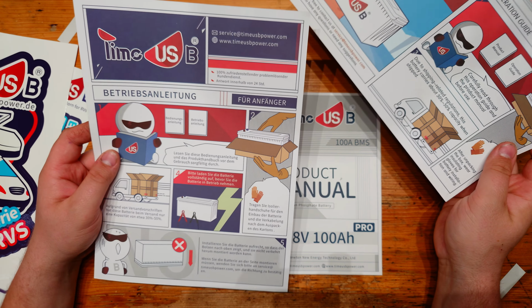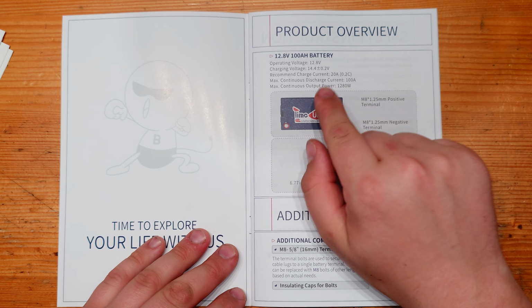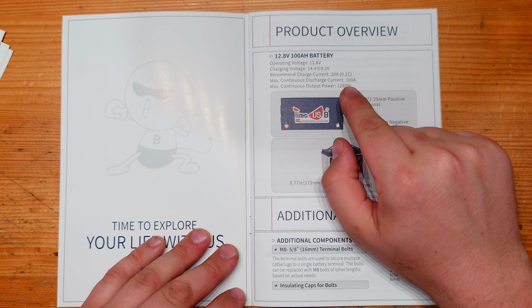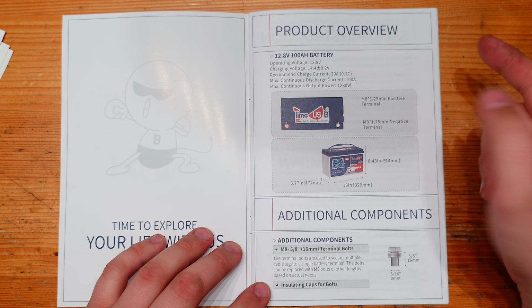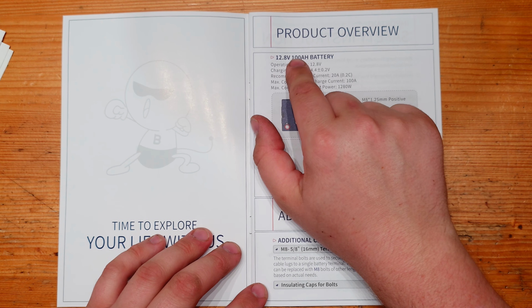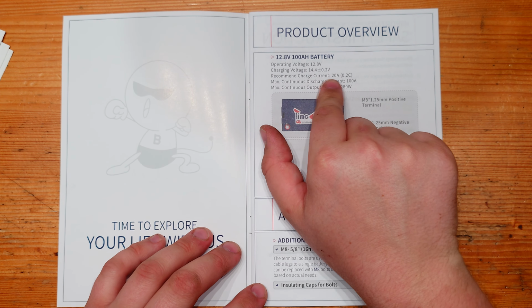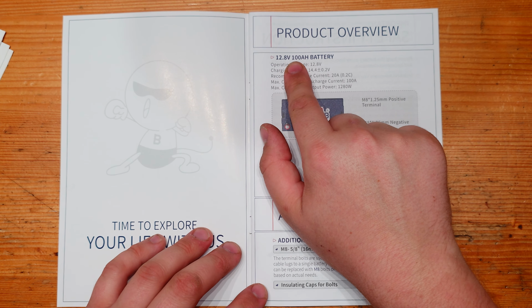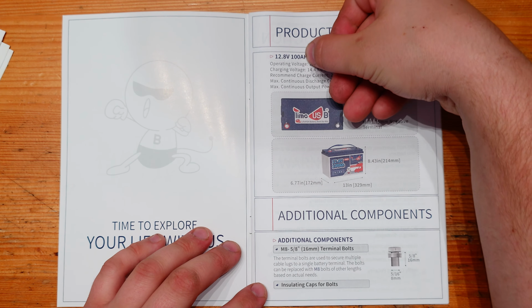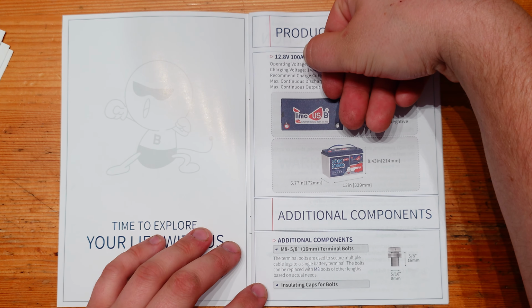All the parameters of the battery can be found on the TimeUSB webpage or in this manual. The recommended charge current is here just for longevity purposes, as lithium ion and LiFePO4 cells are best charged with 0.2C current, which is 0.2 times 100 amp hours, giving 20 amps. It's very easy: you just multiply the capacity, the 100 amp hours, with the C number. So 0.2 times 100 is 20, and the C just means you remove the H and you have amps.